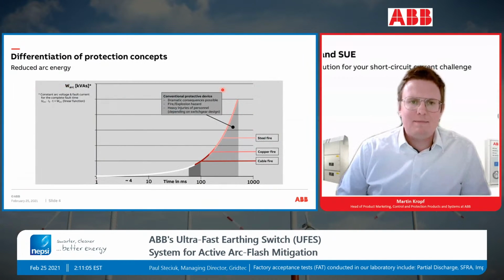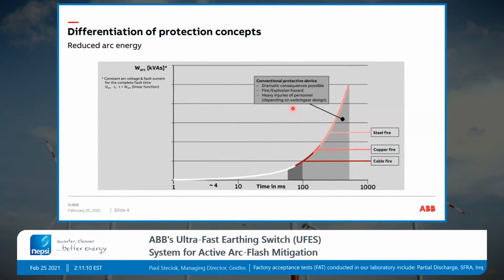Looking shortly at the timing, I prepared this here to just show you what energy level we really have over time if we are facing an internal arc. Let's look at the conventional protection that we normally have installed, which means we have a standard relay, first of all measuring current, and then it sees, oh, there is an overcurrent, oh, what is it, it's probably an internal arc, okay, I have to switch off a breaker. It sends a signal to the breaker. The breaker then decides, okay, let's open, it opens, and then we have an interruption.